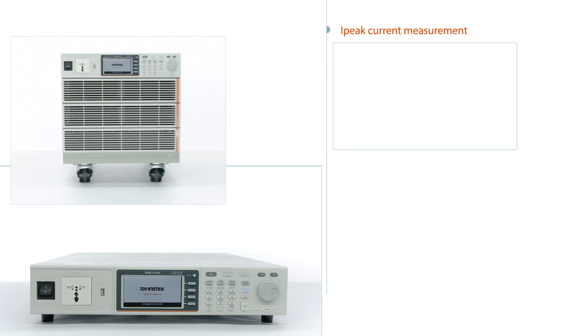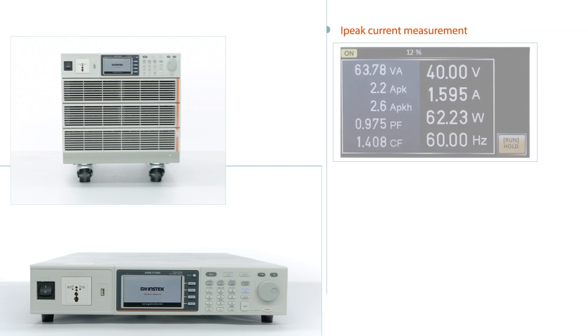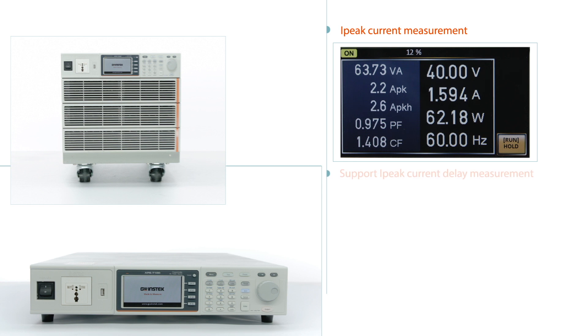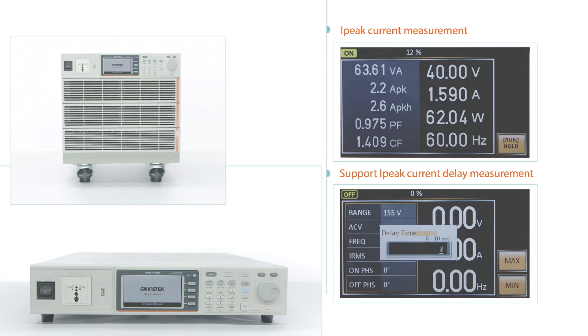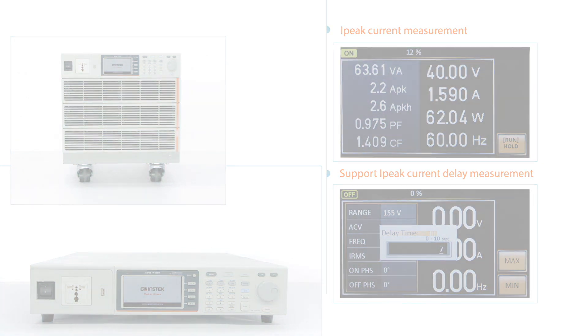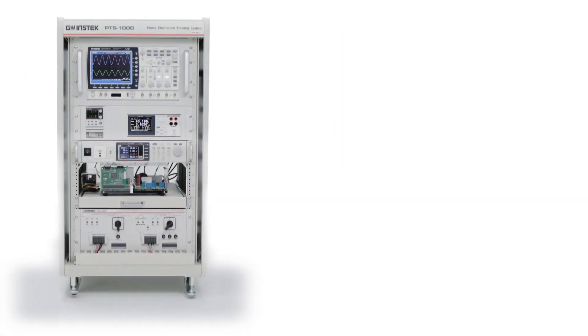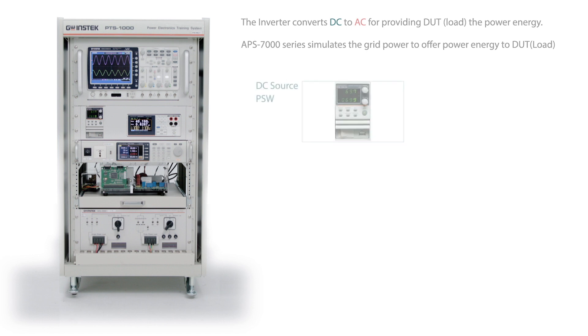Ipeak current measurement is for measuring transient inrush current as soon as the equipment power is on, which is usually done by oscilloscope and current probe. Ipeak current delay measurement is for measuring transient inrush current after a delay of a specific time.